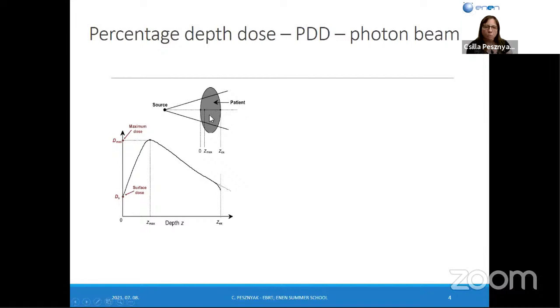You can see here the photon beams. Here is the source, the patient, and there is some special point. If you look at this graph, here is the dose in percentage. We always measure the maximum dose. It is the first and most important. The maximum dose depends on energy. And here is the surface dose. You can see that the surface dose is not the same as the maximum dose.